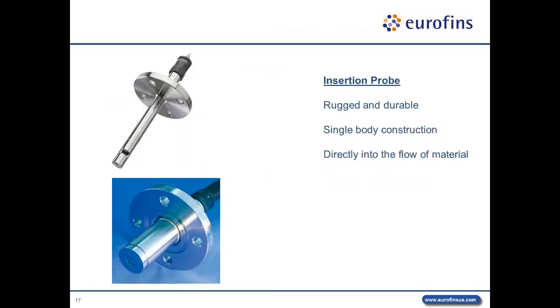The insertion probes are large, rugged probes that are capable of handling high temperatures, high pressures, and high flow rate conditions. They're single-bodied probes which eliminate unnecessary points of failure. They are normally fabricated out of stainless steel. However, other materials are available in the event of highly corrosive or extreme pH environments. Insertion probes are often accompanied or installed into gate valves, which allow for the extraction of the probe for cleaning without interrupting the flow of material in the pipe.